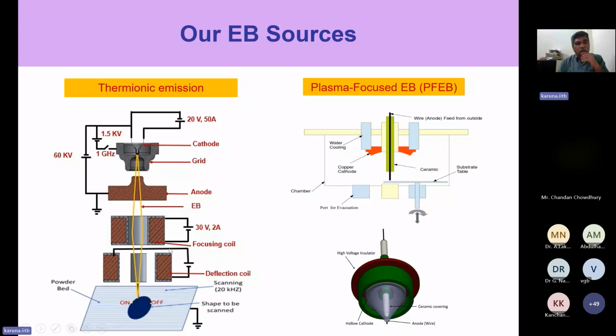Now in between we have a lot of other things. Electrons, they come and then the anode has a 4 millimeter hole. So the beam coming out will also be almost 4 millimeter in diameter. So here we have a coil which focuses it. It's a simple coil creating a magnetic field. Under the influence of the magnetic field, all the electrons are pushed towards the center. So focusing happens. And then you also have deflection coils, one pair for X, another pair for Y. So when you put different voltages to this deflection coil, then the electron deflects towards or away from it. By using the deflection coil, you can position the beam anywhere at the scanning rate of something like 10,000 meters per second, because there's no inertia. It's only the current flow you change. There's no inertia. So this is how it works.